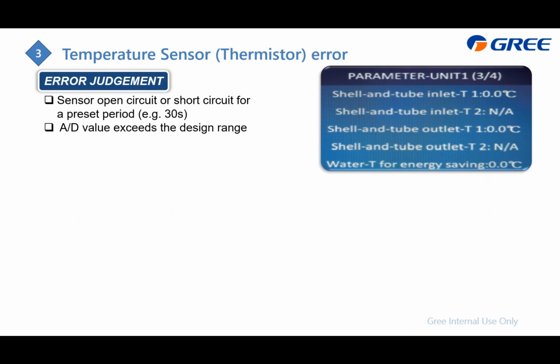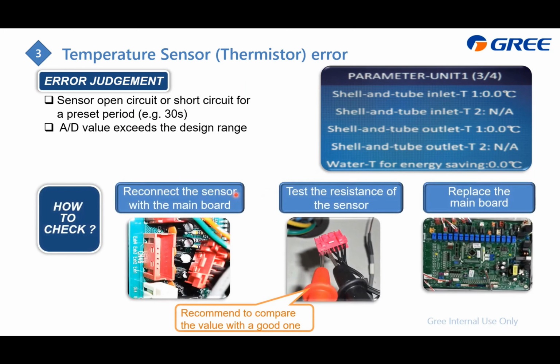First, I will introduce how the system will judge or display this temperature sensor error. Actually, the system always gets the AD value from the sensor. If this value exceeds the upper or lower limit for 30 seconds, for example, it will display this error. So you can also double check from the display here. And the checking method is first to reconnect the sensor to this connector, and then to check the resistance value. Just compare with the standard resistance value whether it is okay or not.